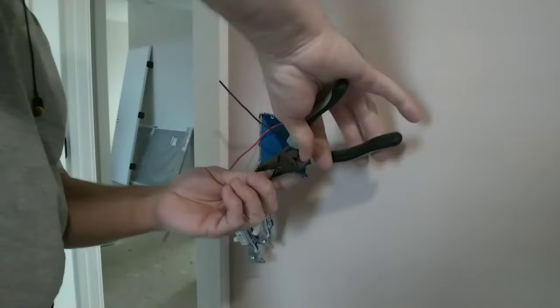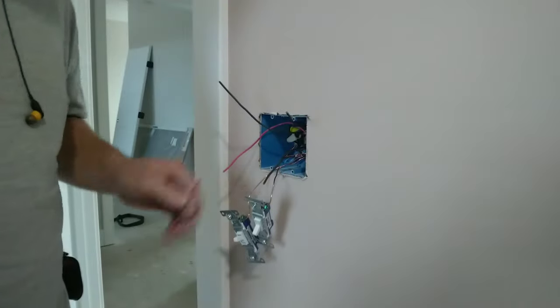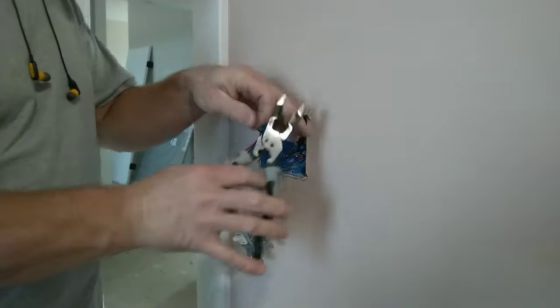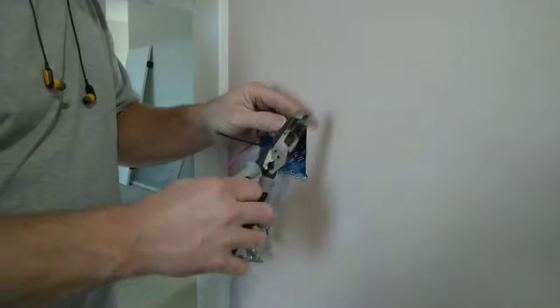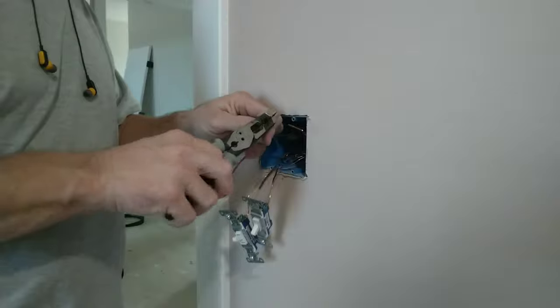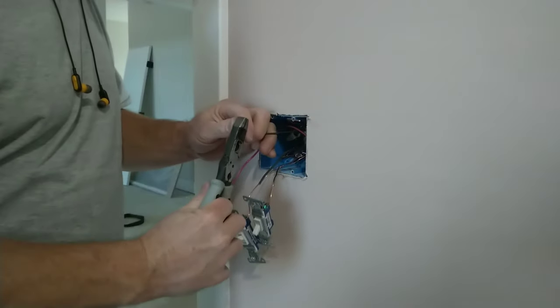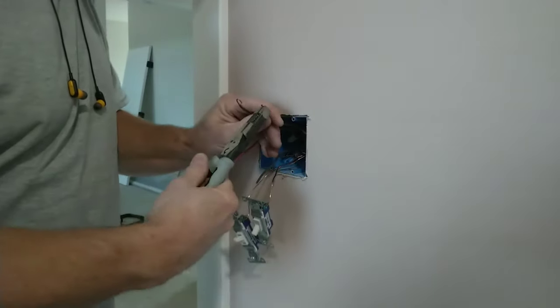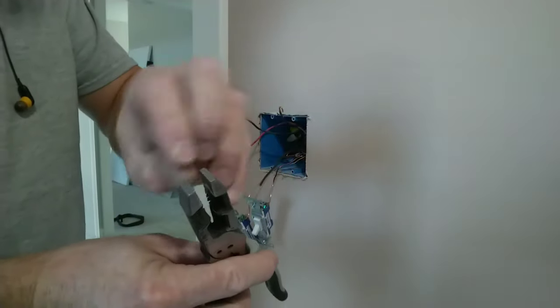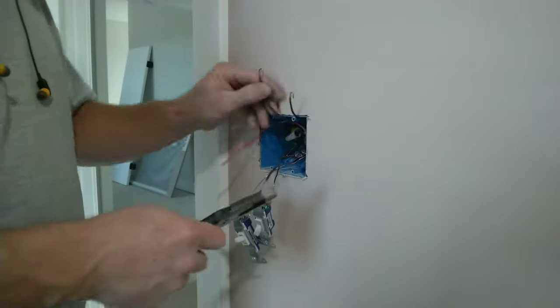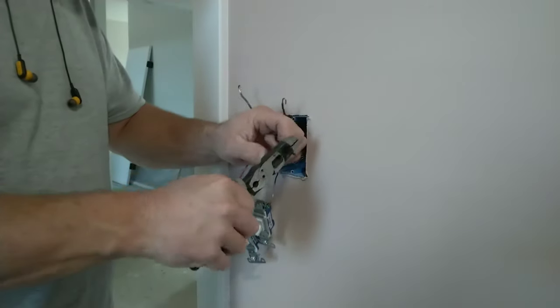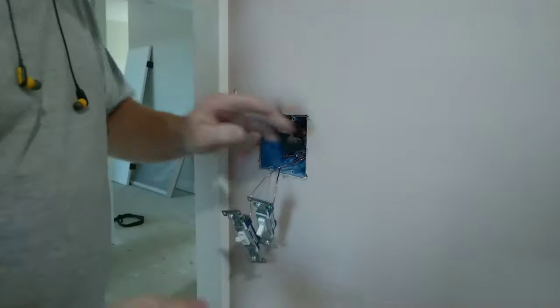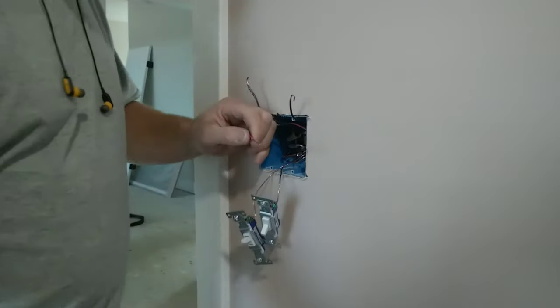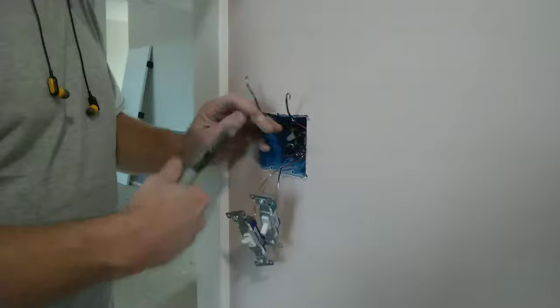I'm gonna cut these wires to an even length hanging out of the wall. I'm gonna cut a little bit on this one and a little bit on this one, so they're all pretty much even. I'm gonna strip back, 7/8 to 1 inch. Grab 3/8 of an inch and curl it to make my hook. Now this jaw thickness on this plier makes a nice thickness for the actual termination of the screw. And I got my trash box I'm launching this stuff into. Some of it I'm hitting, some of it I'm not, but it makes the cleanup a little easier for later.